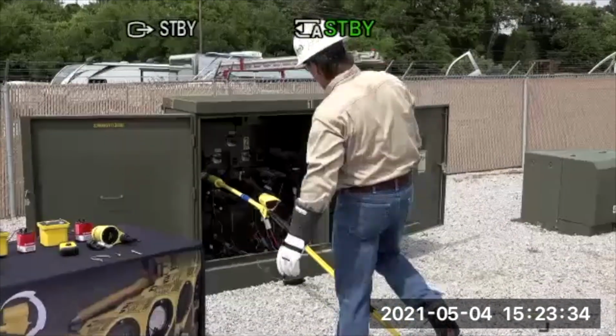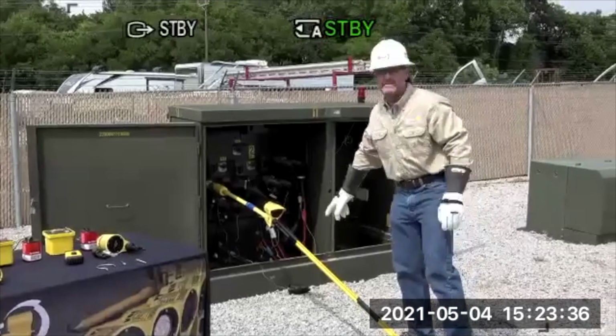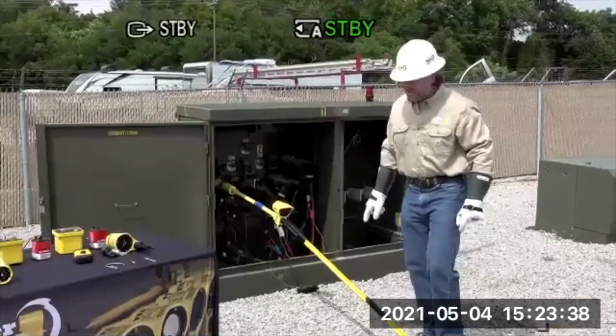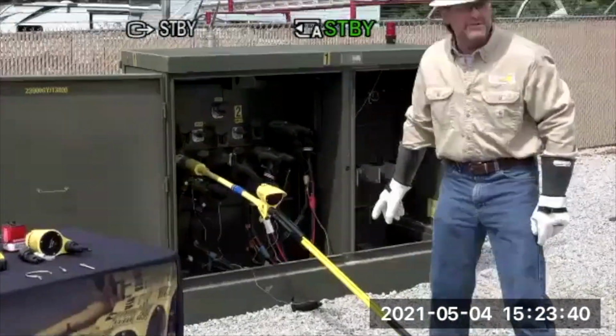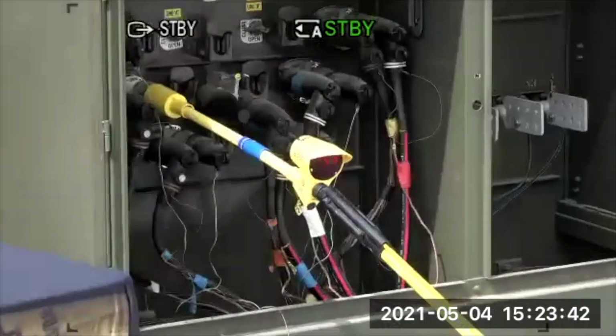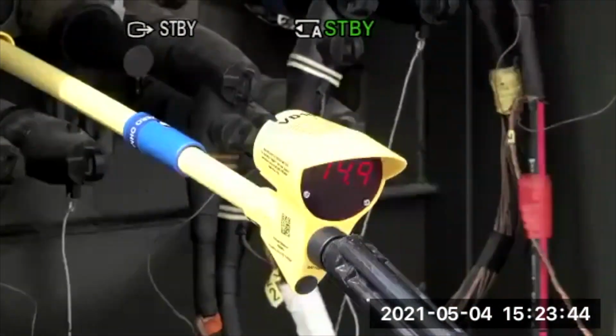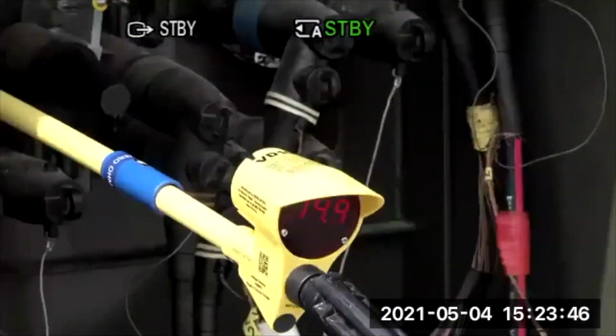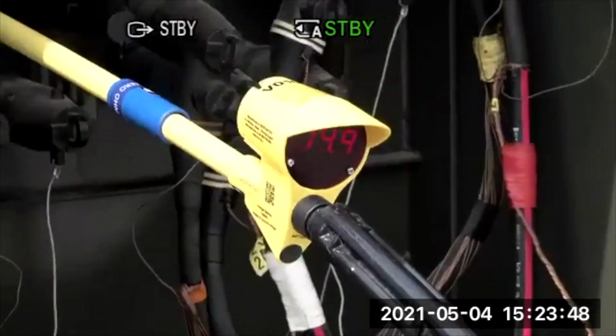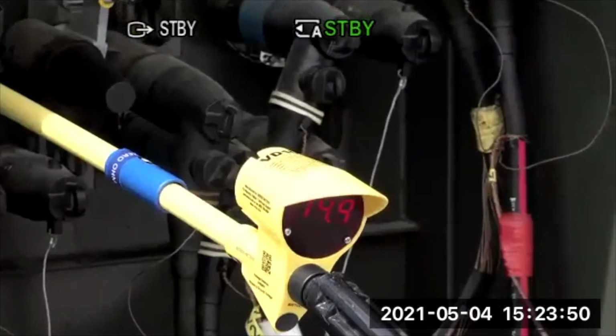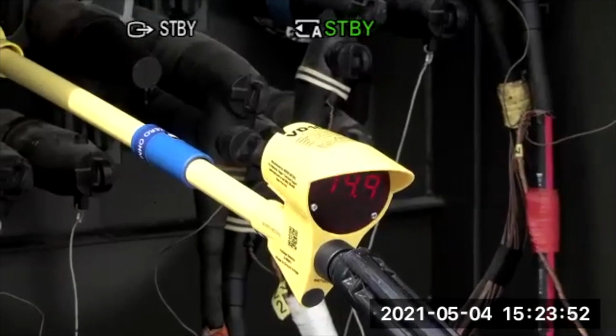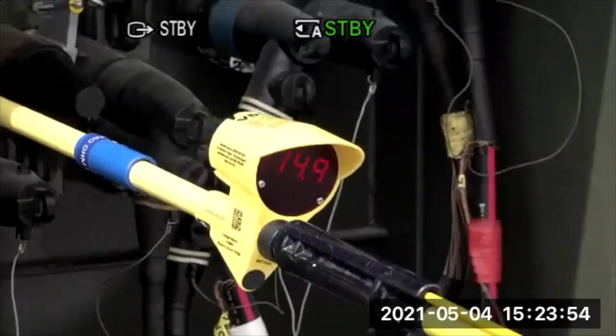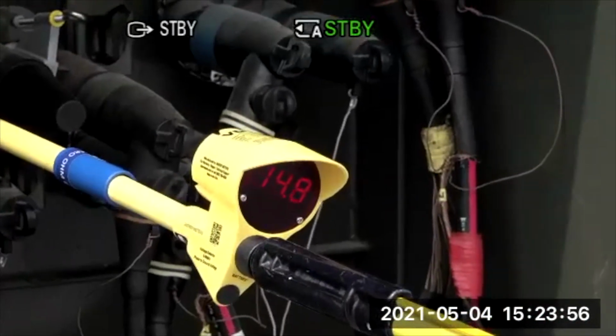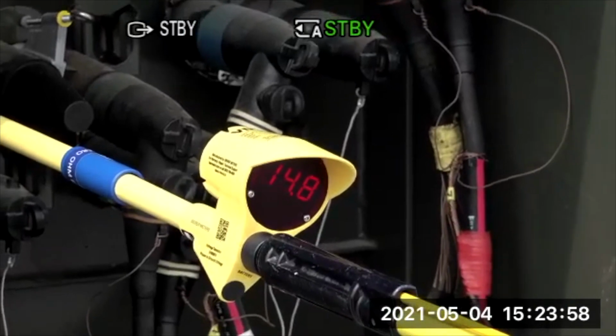Can you see that, Parker? You guys remember what we were reading prior to on this 13.8? We were getting over 16,000 volts, remember that? And now look—now we're getting closer to the true voltage of that 13.8. We're getting about 14.9. You guys see that?